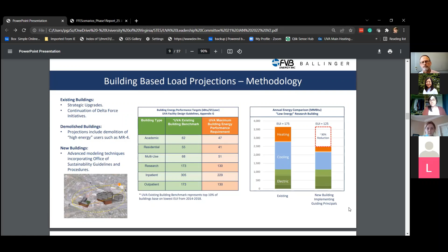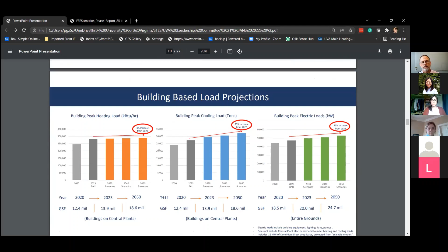These are the peak load projections for heating, cooling, and power. It's not much of an increase considering a 33% increase in building load. The cooling load goes up because we're going to use things like building engagement to actually increase cooling in the wintertime, so we can run our efficient heat recovery chillers then to make heat.